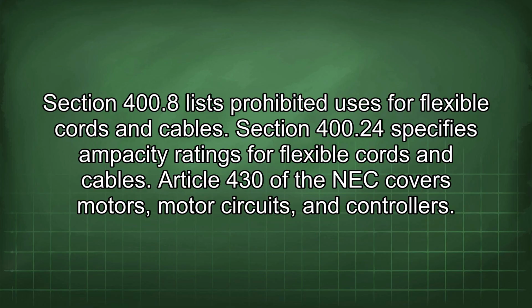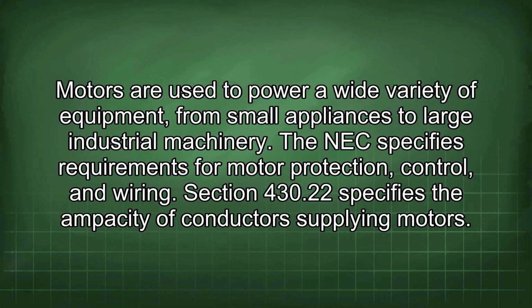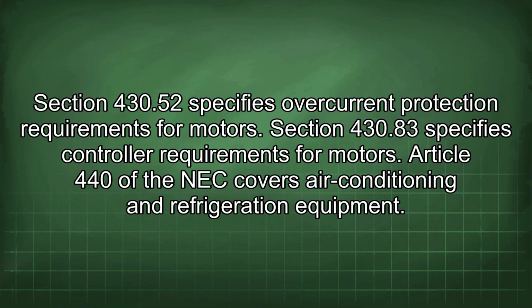Article 430 of the NEC covers motors, motor circuits, and controllers. Motors are used to power a wide variety of equipment, from small appliances to large industrial machinery. The NEC specifies requirements for motor protection, control, and wiring. Section 430.22 specifies the ampacity of conductors supplying motors. Section 430.52 specifies overcurrent protection requirements for motors. Section 430.83 specifies controller requirements for motors.